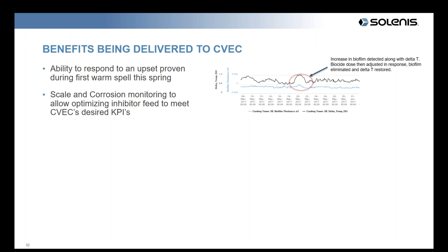The OnGuard instruments also allow us to monitor for scale and corrosion, which allows us to optimize our inhibitor feed rates. About a month and a half to two months ago, we started incrementally reducing our scale and corrosion inhibitor dosage concentration, and we've reduced that by about 10% to date without experiencing any adverse effects or any increase in fouling factors or heat transfer deficiencies. So the OnGuard systems are very helpful in providing that real-time data.